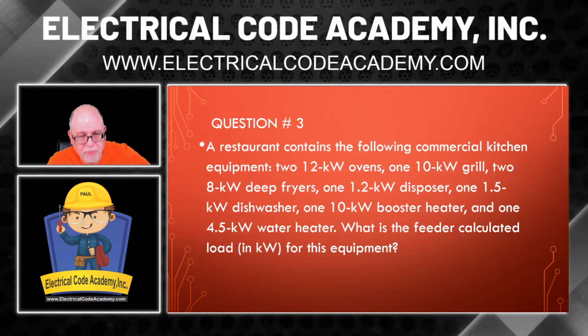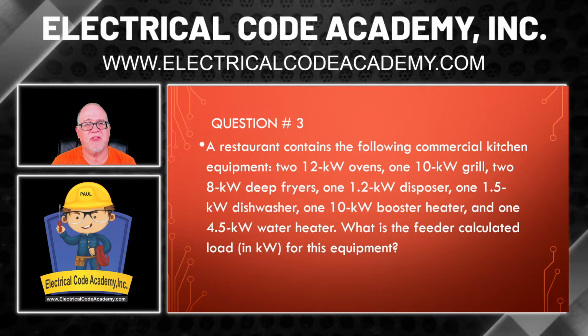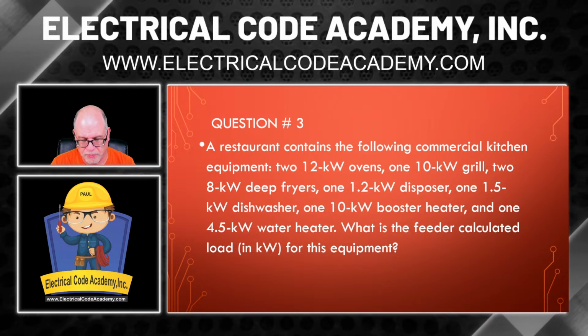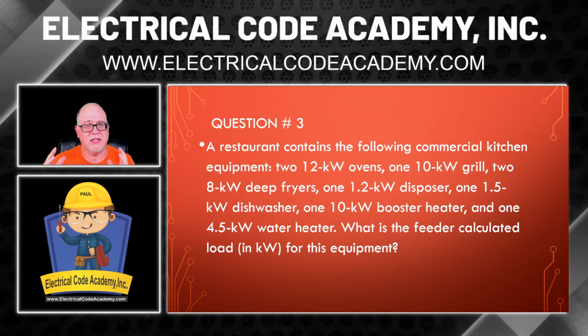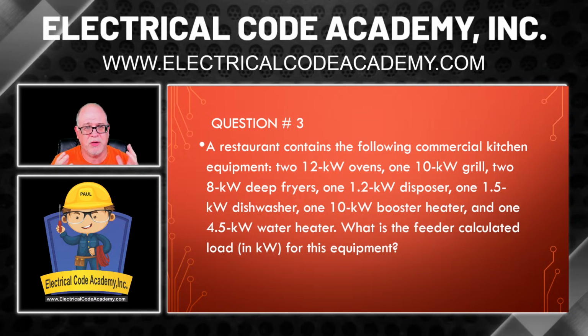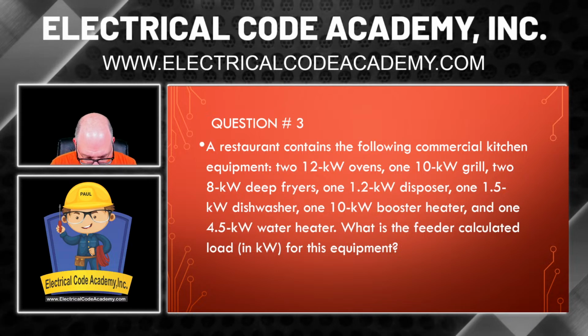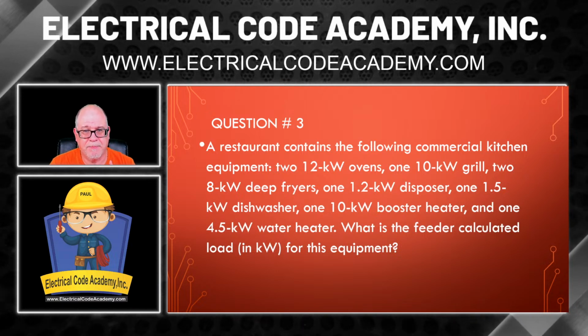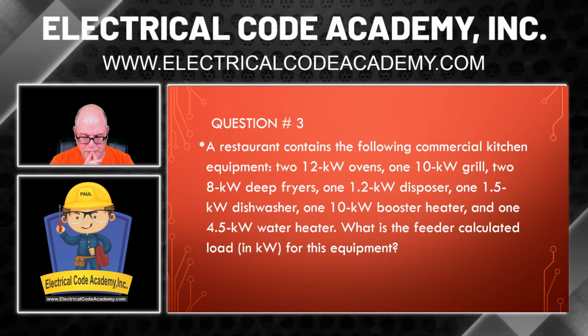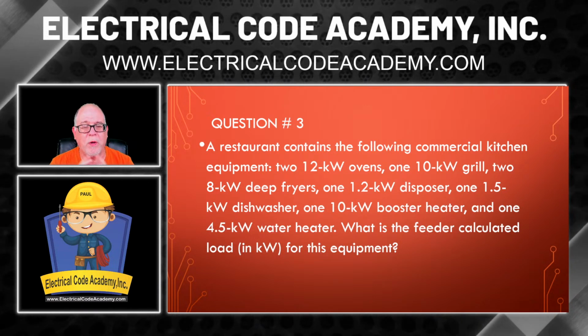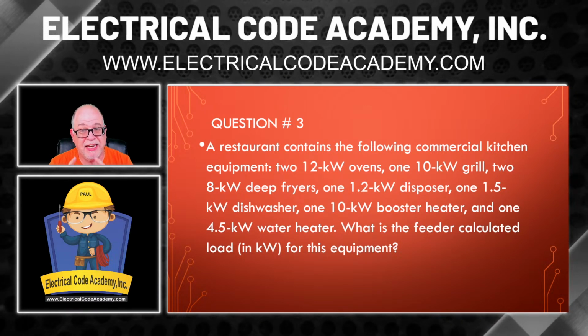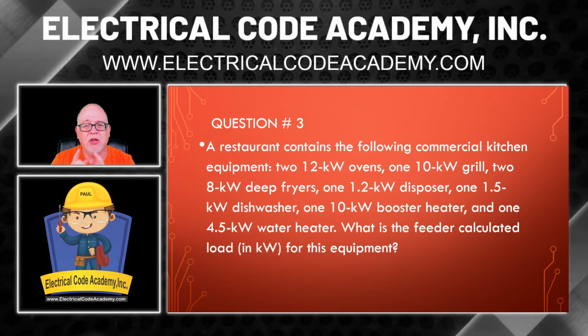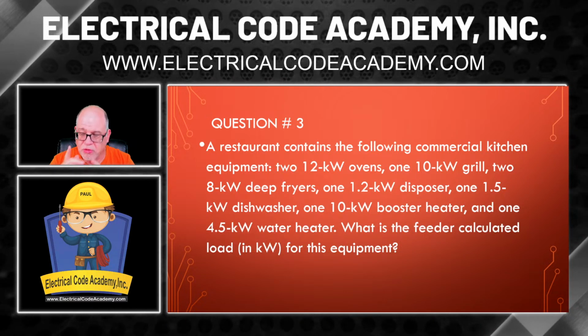All right, and we're doing a feeder, so that makes sense for what we're doing here. We're feeding a panel that's got just these loads in it, maybe, and that's what we're sizing this feeder for. Okay, next thing is we look at it and see that there's a demand table there, and it's talking about calculated, so there's something I need to do. So we're going to go back to the code and see what the code permits us to do.